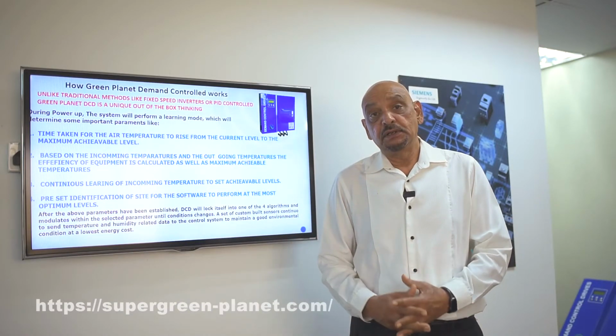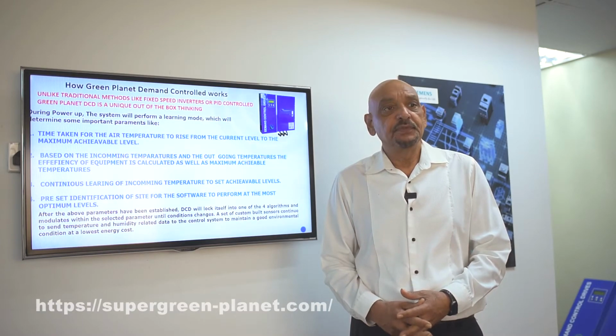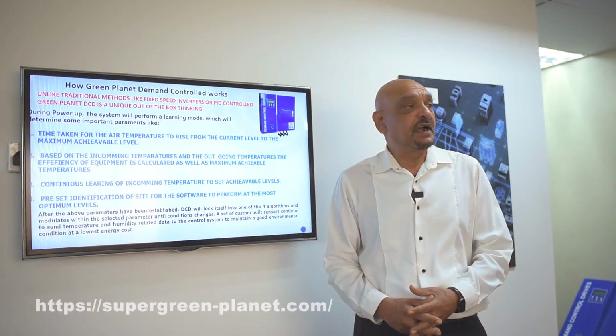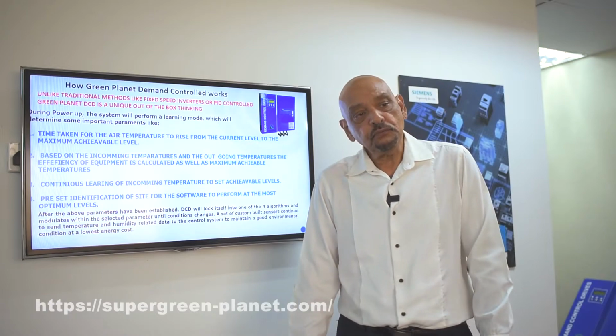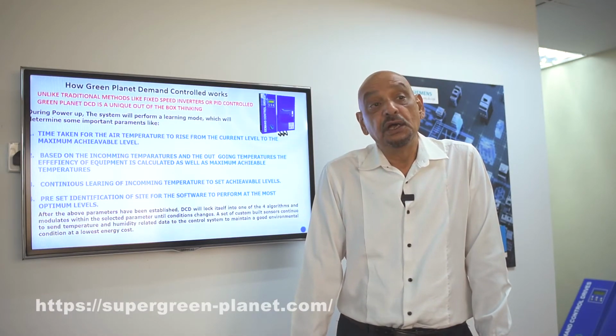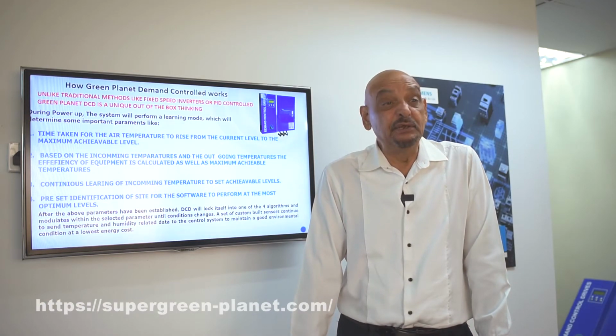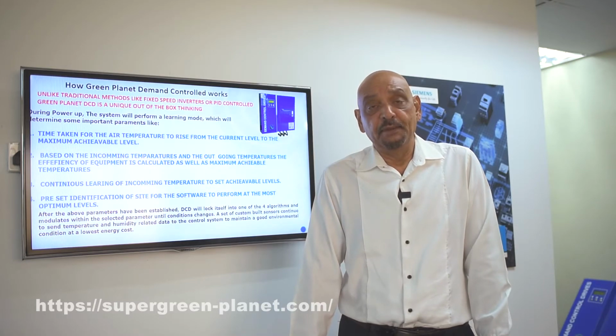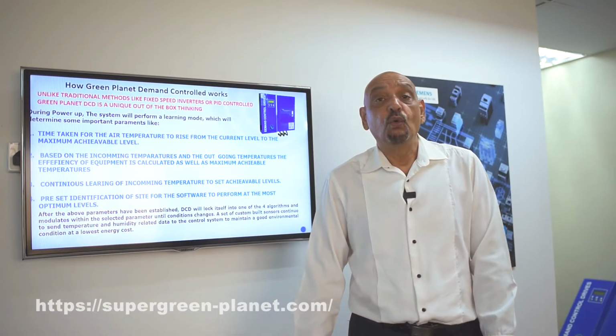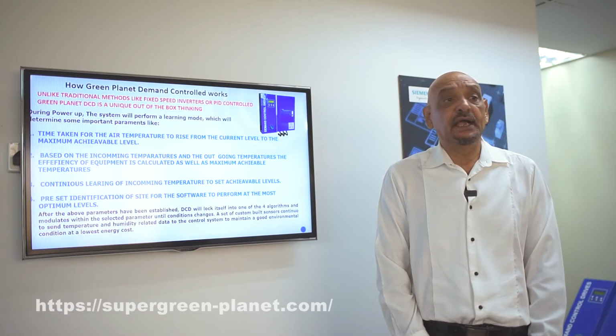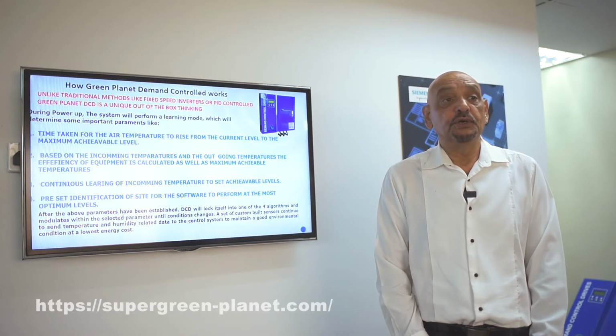Now, the principle of managing your cooling tower is the same, except that the software is different, in the sense that as far as your cooling towers are concerned, you will need to measure your incoming water temperatures. Here also we use in-house built and designed submersible temperature sensors. The temperature sensors are fitted within the water flow, so we will measure the incoming water temperatures, we will measure the outgoing water temperatures, and at the same time your ambient temperatures are measured, and the system would then make a decision as to what is the efficiency level of your current air handling unit, and from that point onwards, the motor is driven accordingly.